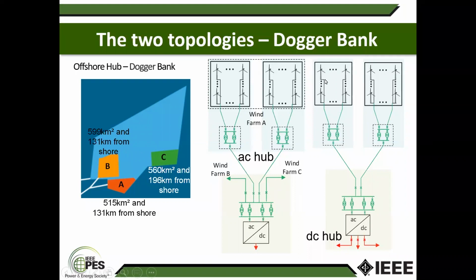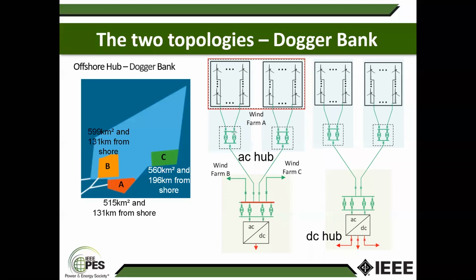Let me use small. Yeah, this is one of the wind farms, I'm going to call it wind farm A, and wind farm A, B, and C need to be connected together. So you can see there is an AC connection, and everything comes into that bus bar. The power coming from wind farm A, I'm only showing you two small parts of that wind farm, but it may have more than two modules. Then the power from wind farm B comes to the same bus bar, and power from wind farm C comes to the same bus bar. Then you use an AC-DC converter and convert it to DC and send it to the mainland through a DC link. Now this one is called an AC hub because the connection is through the AC bus bar.